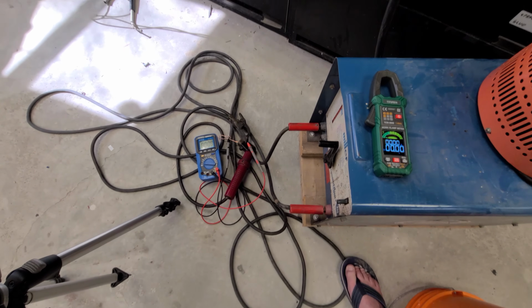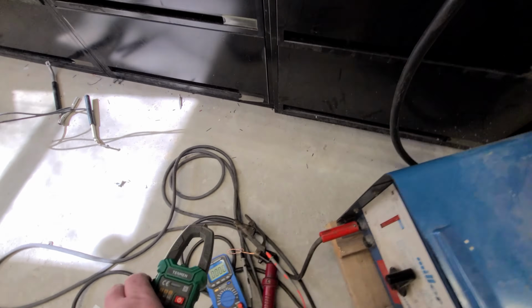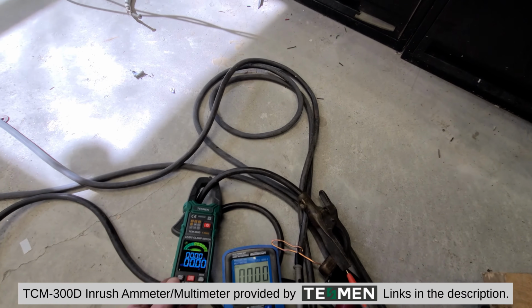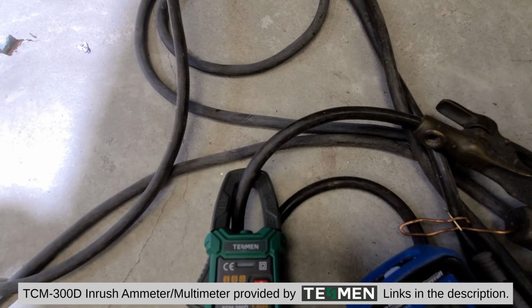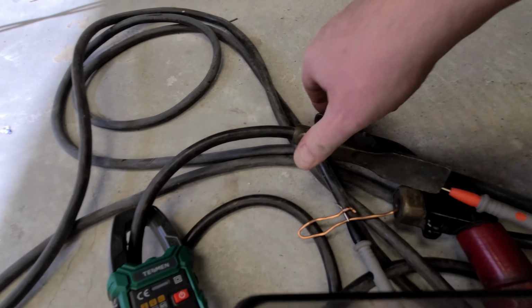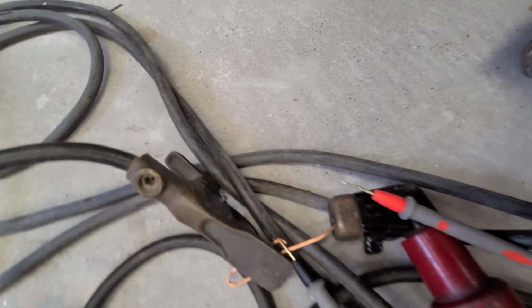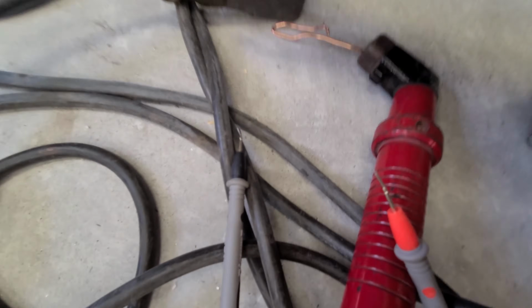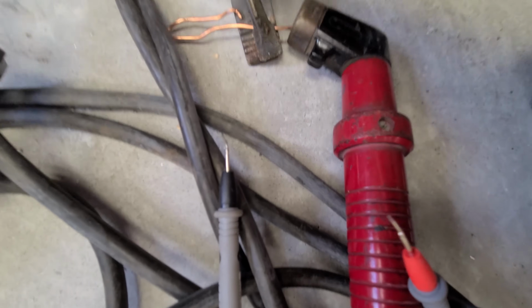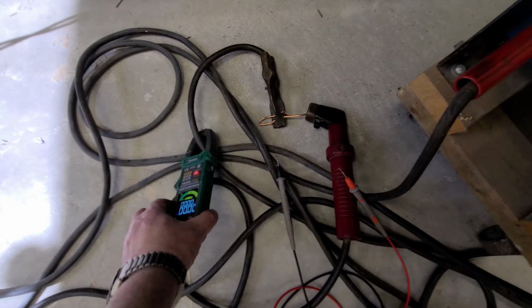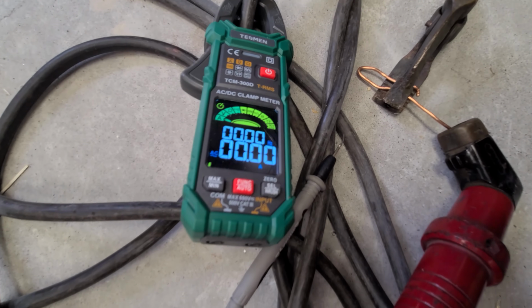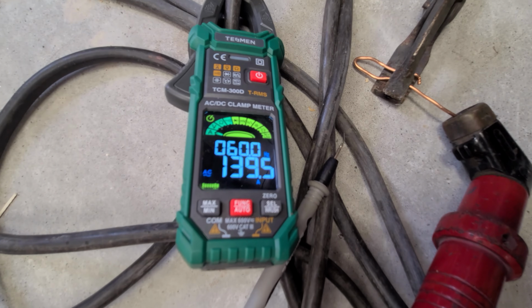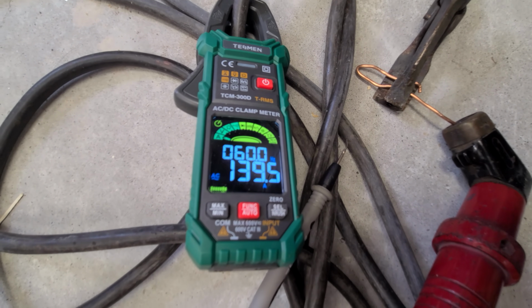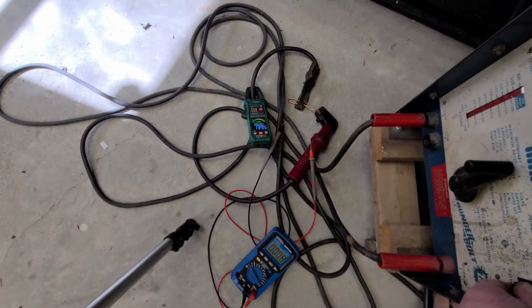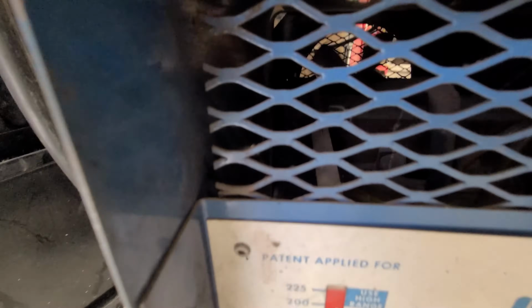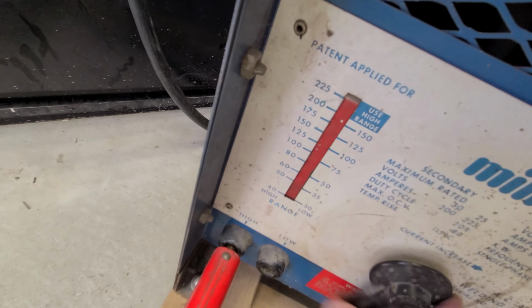Now that we've done that, we're going to get the short circuit current. I'm going to take the trusty ammeter and just put it around the wire, and connect our return current thing. So we've got a short here. I'm going to move this over because I don't want to melt the insulation on my welder cable. We'll turn on the welder and see what we get. We get about 139.5 amps.